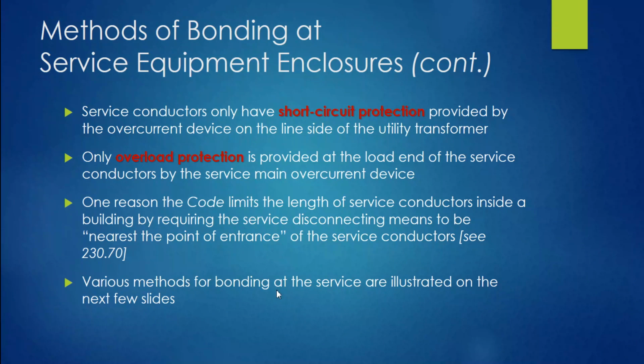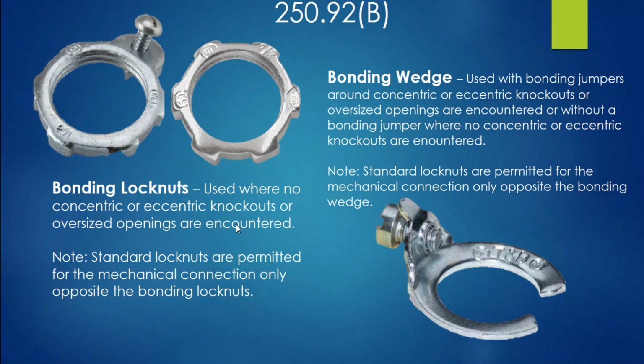Various methods of bonding at the service are illustrated on the next few slides. So here are your bonding lock nuts. Again, if you don't have concentric or eccentric knockouts, or you don't have any oversized openings, then you can use one of these. Now, here's a standard lock nut, which might be on the other side of this, or it might be on the outside where the raceway comes to the enclosure. And this is for mechanical purposes, perfectly acceptable. But this is not going to be your means of bonding. This is your means of bonding, as long as you do not encounter any eccentric or concentric type of knockouts.